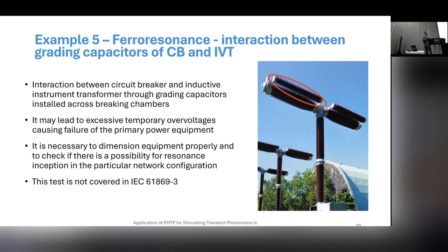So this is a test which is not covered by the IEC standard, but some customers, some utilities, ask for their specific case to do the test in a high voltage laboratory to prove that the inductive voltage transformer that they will install will not get into problems related to ferroresonance. So on the next few slides, I will show the results of that test.